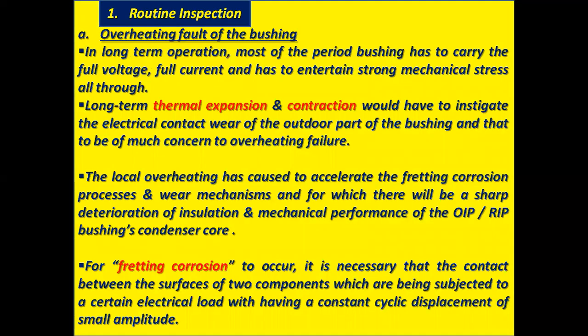1. Routine inspection. A. Overheating fault of the bushing. In long-term operation, most of the period, the bushing has to carry the full voltage, full current, and endure strong mechanical stress all through. Long-term thermal expansion and contraction would instigate electrical contact wear of the outdoor part of the bushing, and that is of much concern for overheating failure.